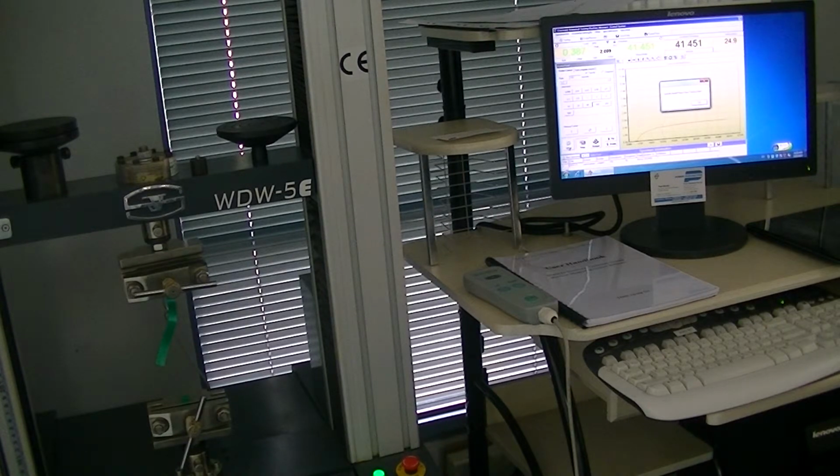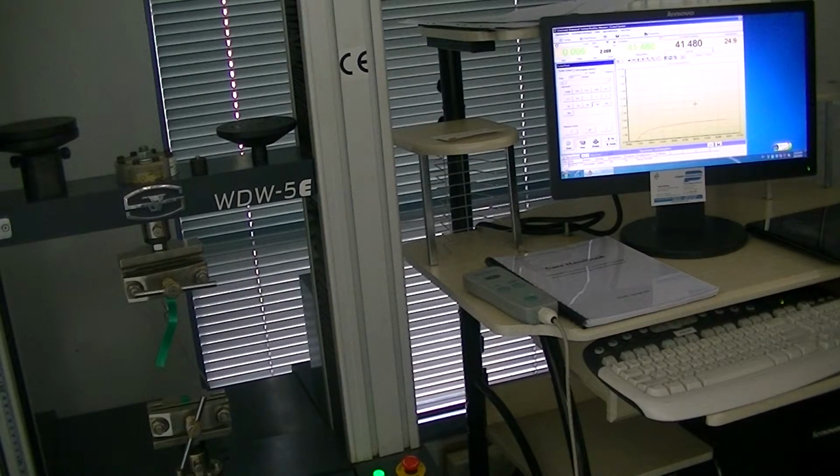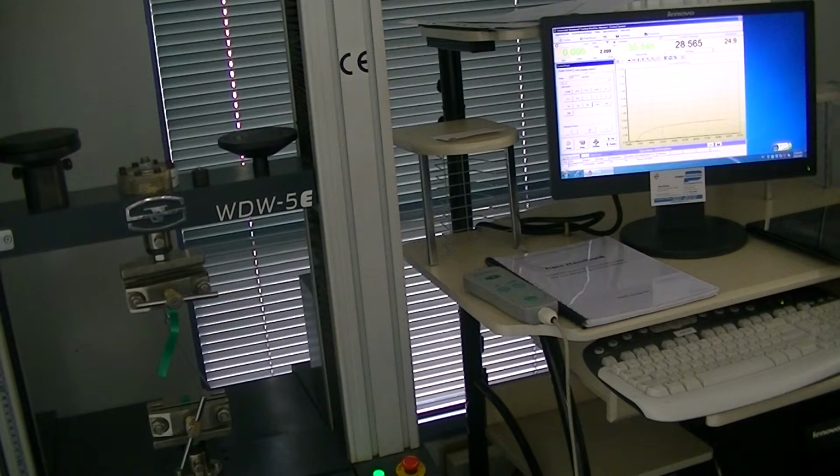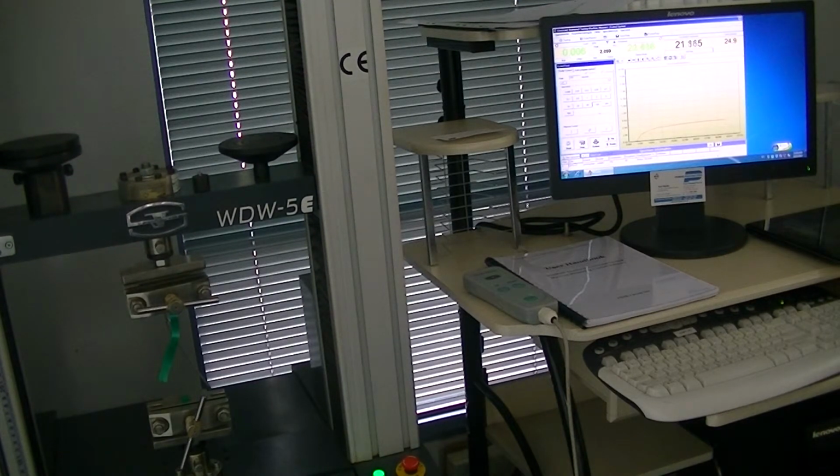And like so, the sample is broken. We click OK to get out of that. We go on to slide number 11. It says, after the testing is complete, to view or analyze, click data process. If you want, we can click return to the start position. That is your call. You don't have to do that. I'll just do it just to show you.